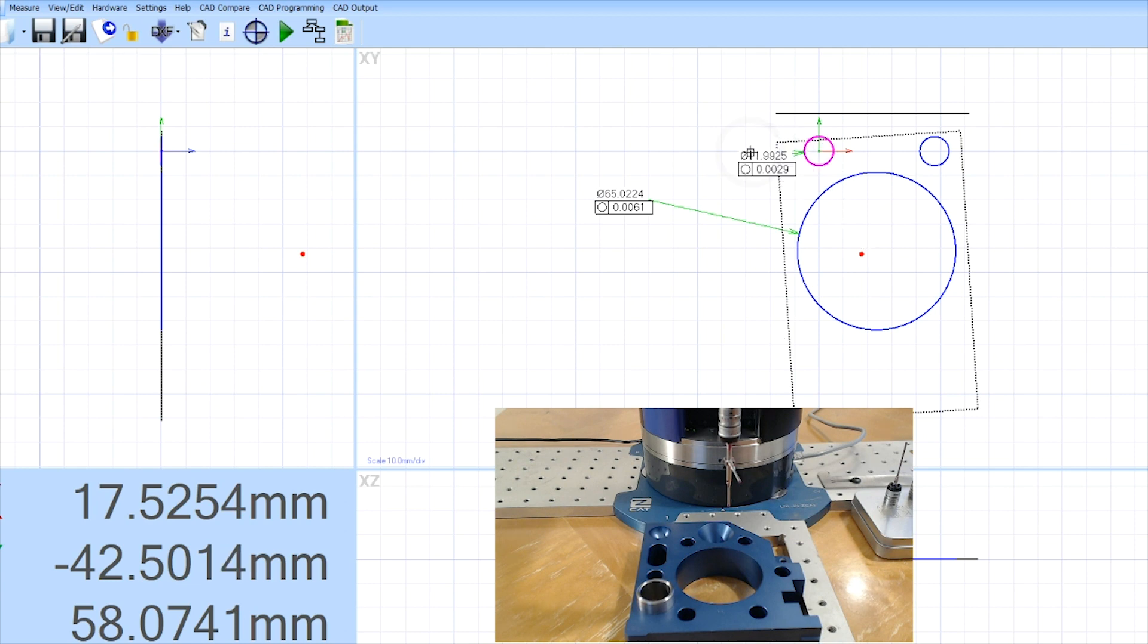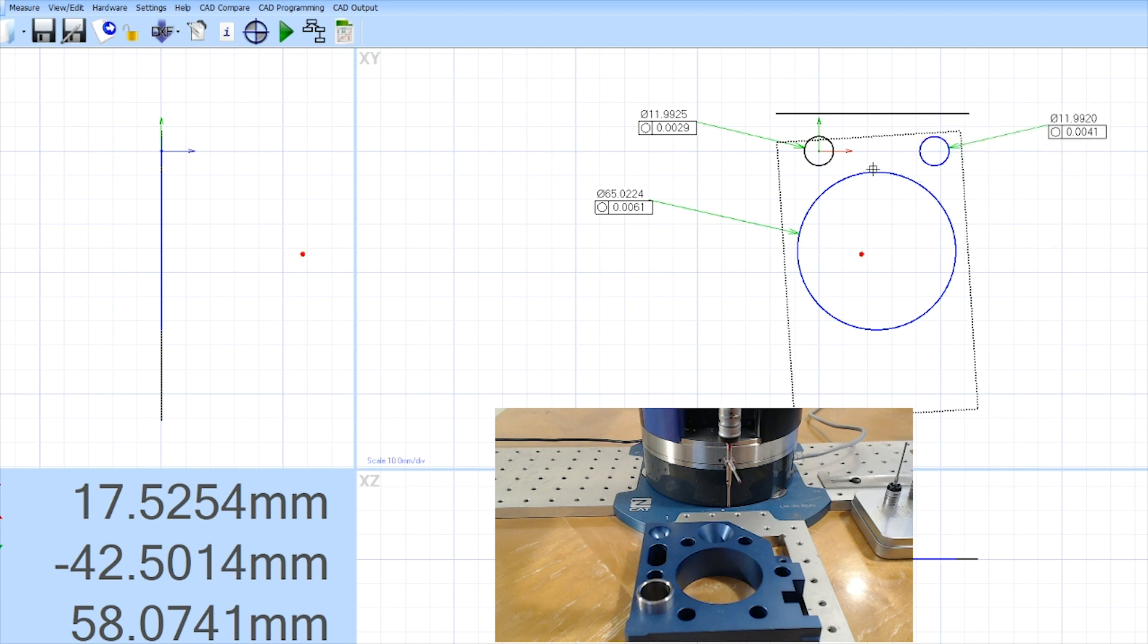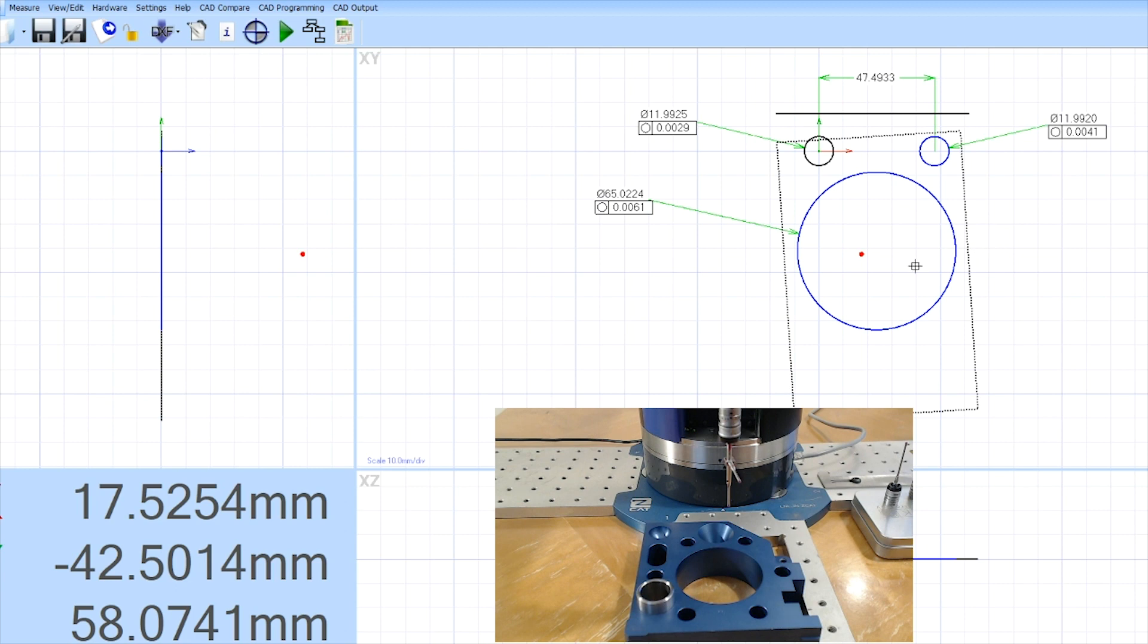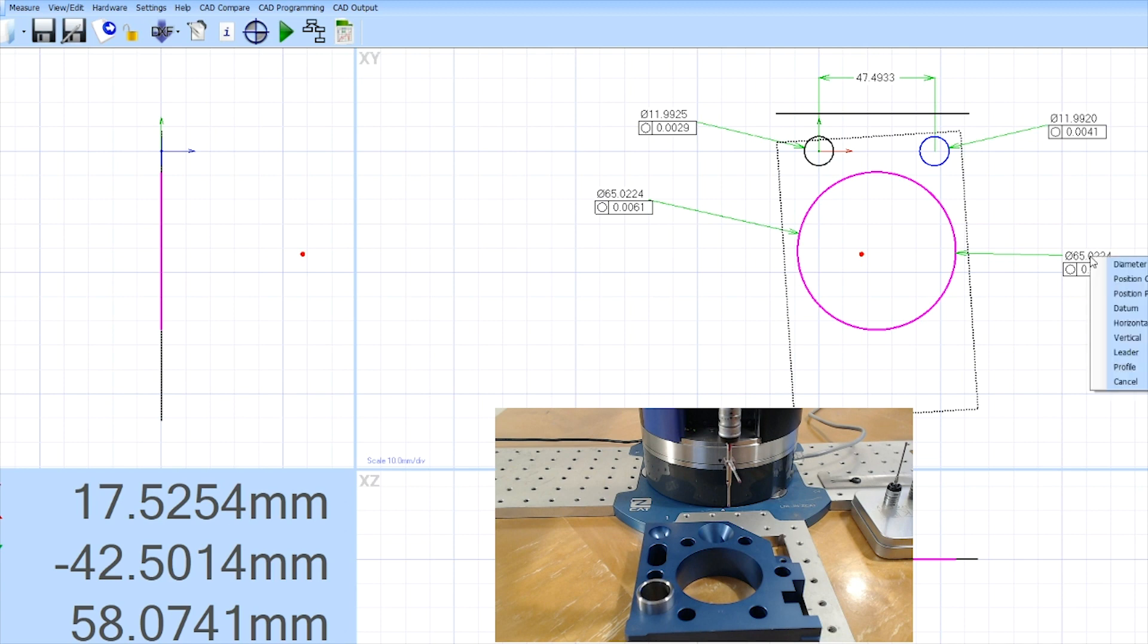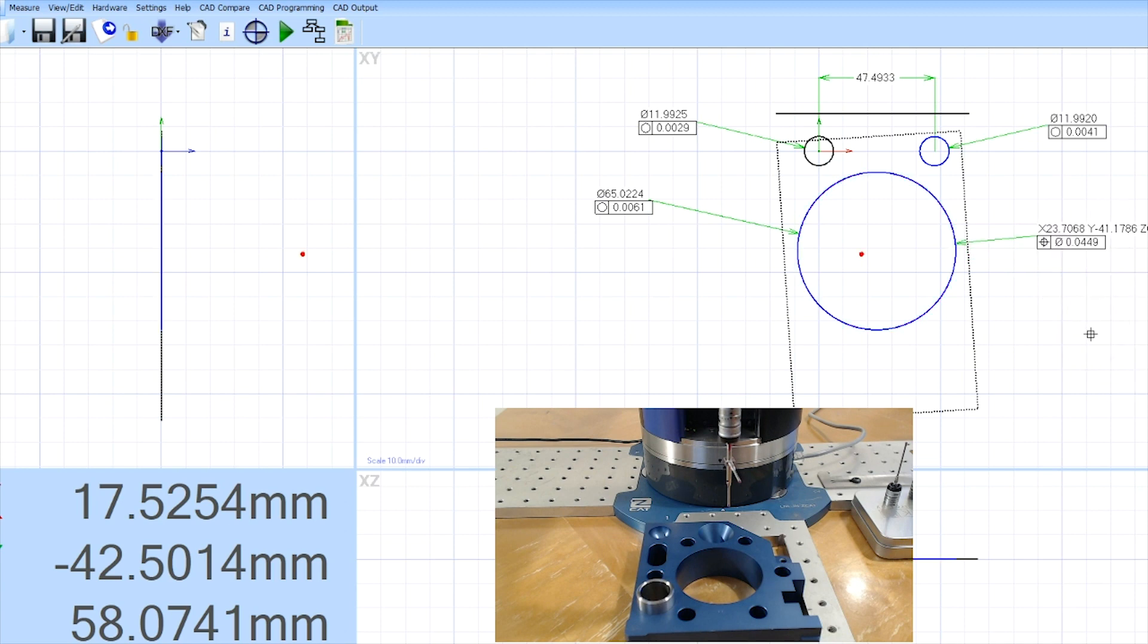Now if I double click on any one of these features I can pull out the results. Obviously those are diameters. If I want to know the distance between two features I can click once on each, pull it out, drop it, and that's the distance between these two features. If I wanted to get true position I could double click on this large diameter and then right click and say position cartesian and it will give me the true position. That quick, that easy.